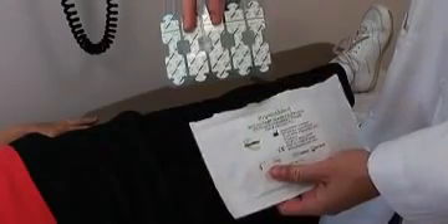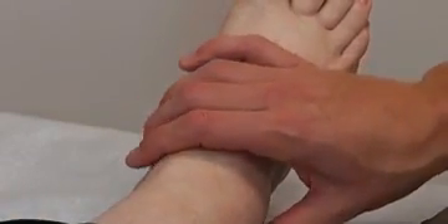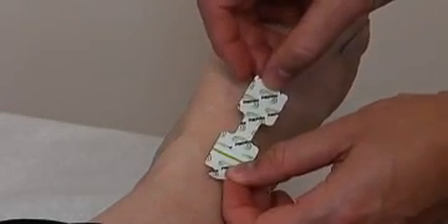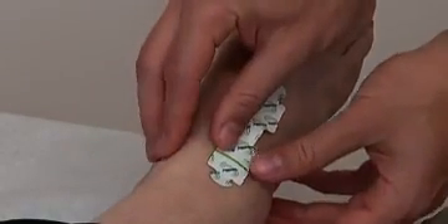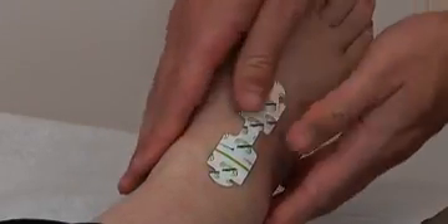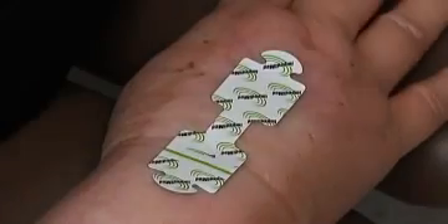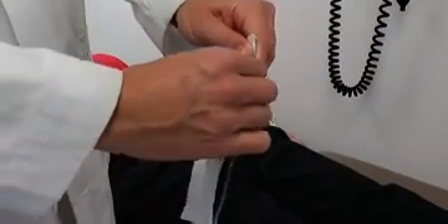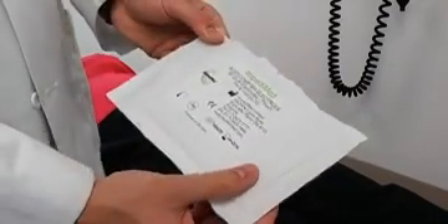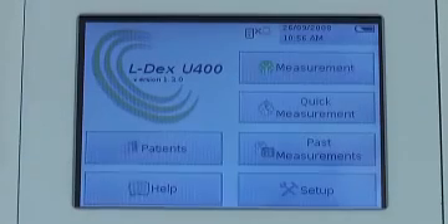Remove a sheet of ImpediMed electrodes from the package. Gently place one side of the dual tab electrode with the green line between the medial and lateral malleolus bones and run the distal tab down towards the toes. One dual tab electrode is placed on each hand. The green line should be placed midline of the ulnar styloid process on the wrist and run the distal end down towards the fingers. When you are finished with the electrode package, use the Ziploc seal to close the pouch to ensure the electrodes do not dry out.